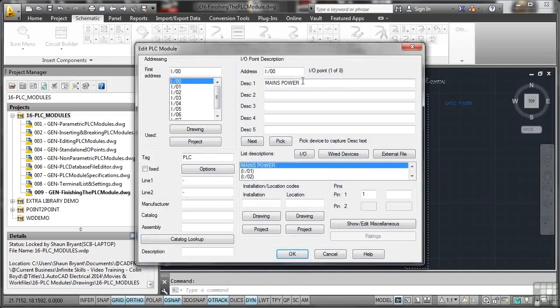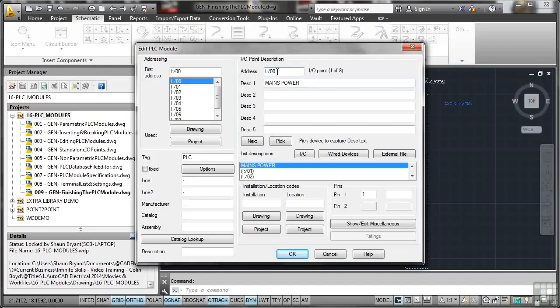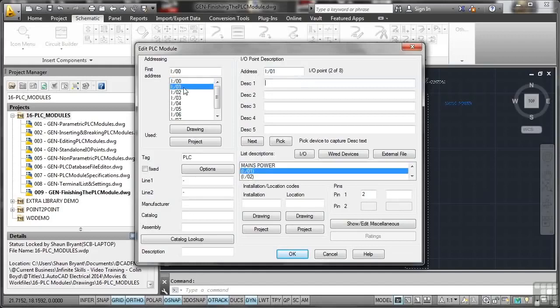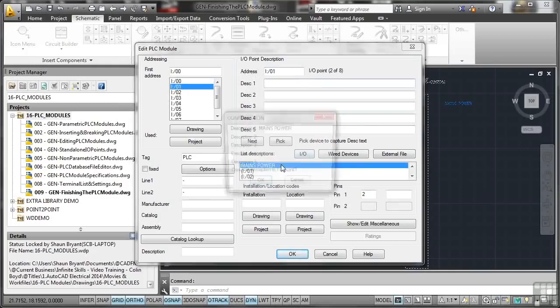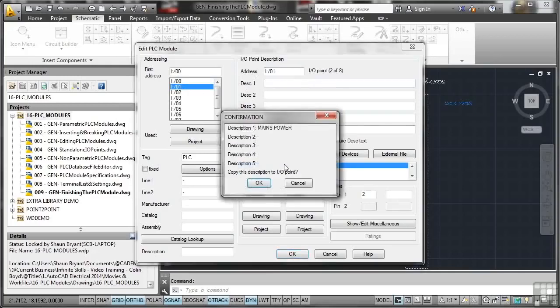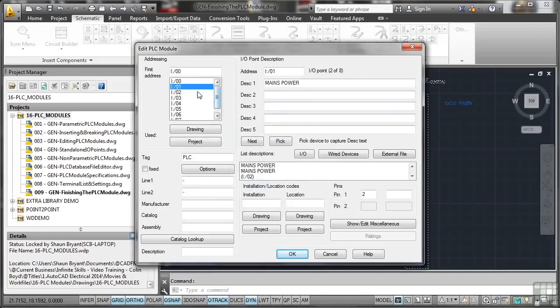You'll notice there's the mains power for my input output point I00, one of eight. If I select it for the next one down, is it there? No, it only does it for the first one. And there it is there, mains power. See description one mains power, description two. Copy this description to IO point. If I okay that now it adds it to the next one and so on. So it only does it for the first one as a default, but you can add it as you go.